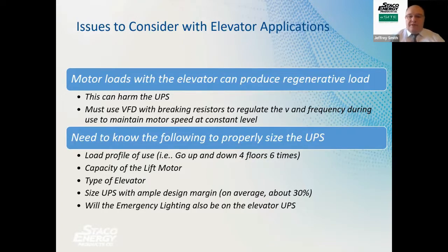Elevator applications, one of the big things we have to look at is motor loads. The reason is that when you turn a motor on and when you slow a motor down, it starts to act like a generator back to the UPS. So we've come up with a system to remove the regenerative power being fed back to the UPS, so we don't overload the UPS and cause damage to it. We're working on load profile uses so we can look at different size systems, the types of elevators, the lift, the feet per minute. It's amazing how many different things are available when you start looking at different vertical markets within the industry.